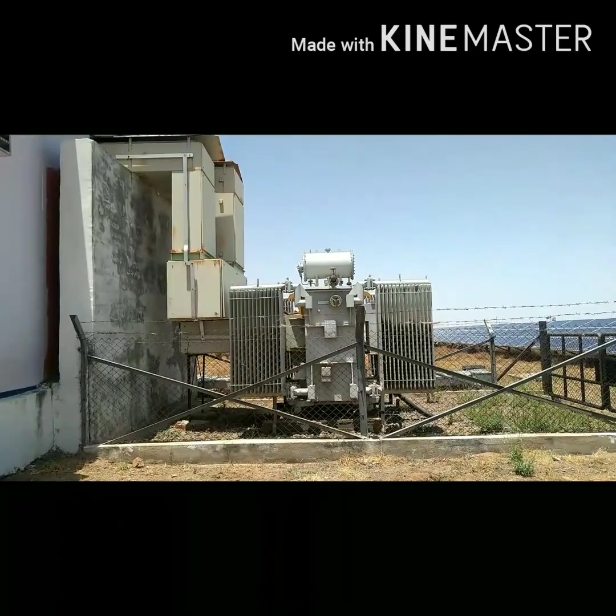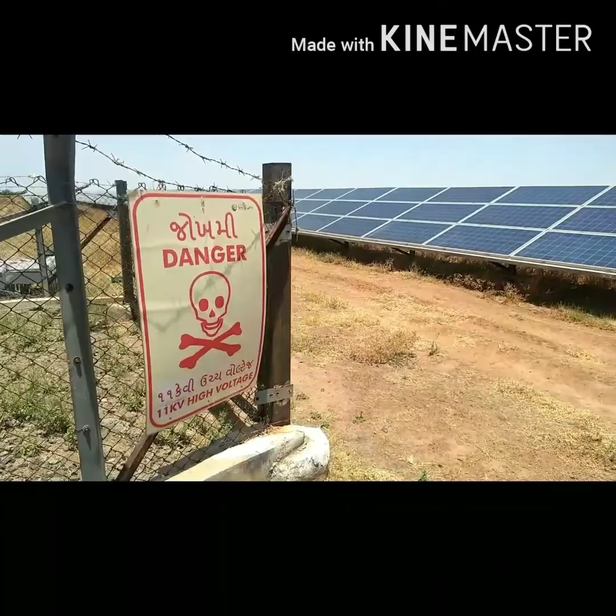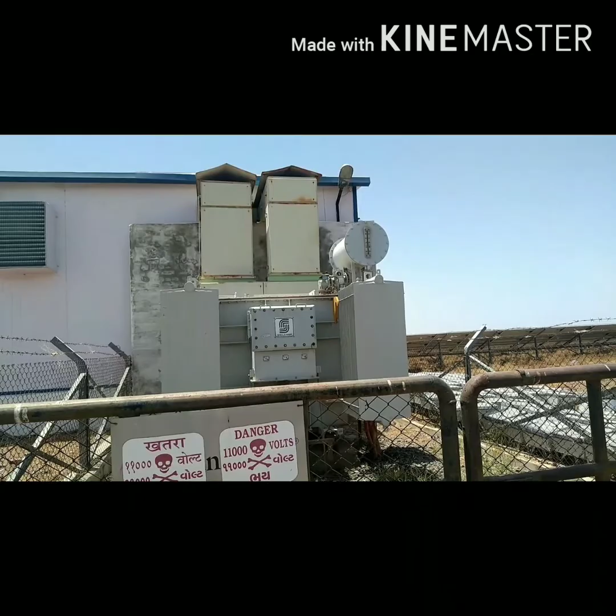This is our inverter duty transformer. The rating of this transformer is 2.5 MVA for the individual blocks. From here we are converting our power from 320 volt AC to 11 kV, which is directly fetched from here to our main control room, where you have already seen our HT panels.